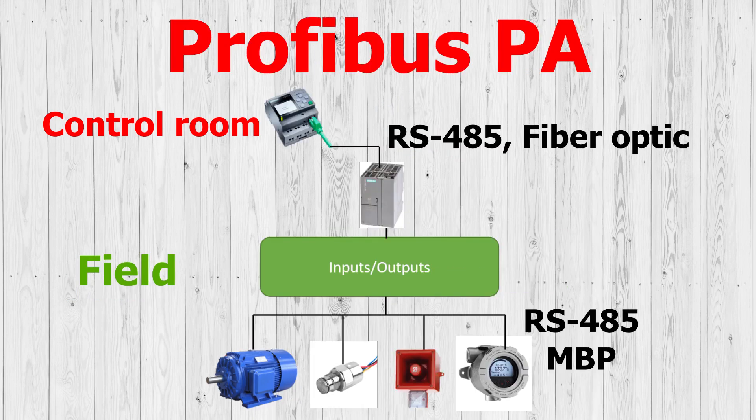Then, Profibus PA, or Process Automation, was created, which can be intrinsically safe or explosion proof. What differentiates it from Profibus DP is that all the cables that go to each of the instruments for their power supply and communication are combined into just one, which saves even more on wiring.